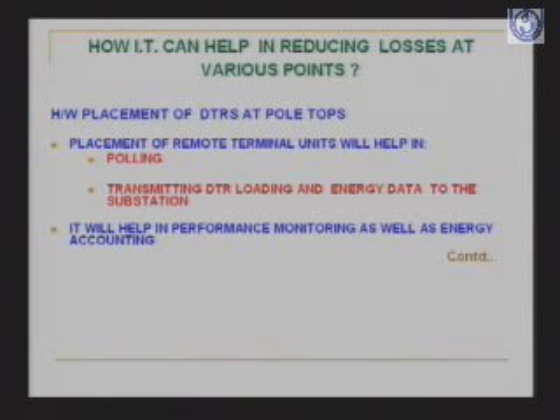Hardware with respect to DTRs at pole tops is essential for distribution. Placement of remote terminal units for polling can go to each of the poles and perform polling, similar to how in a multi-user computer environment the operating system goes terminal to terminal for polling. This is a similar concept for transmitting DTR loading and energy data to the substation.